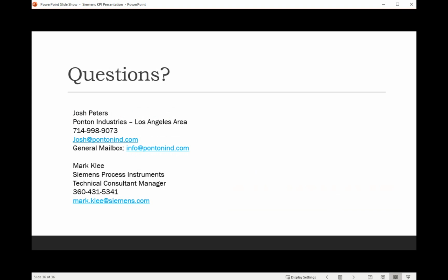What a lot of end users do is they use PDM as a way to document their system. So they will go out and say, today my Hydroranger in this application is healthy and it's working well. And they do two things. Number one is they use PDM to do an upload of all of the parameters within the Hydroranger 200 and convert that to a PDF document that you can either print out or save electronically. And they also do an echo profile, which is, here is what the echo profile looks like today when my system is operating at 100% efficiency, or operating properly.